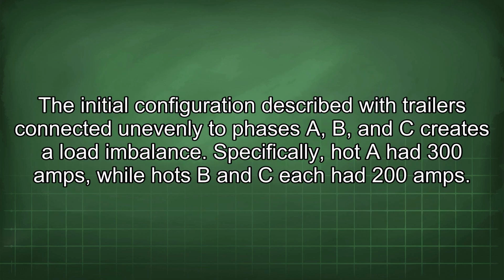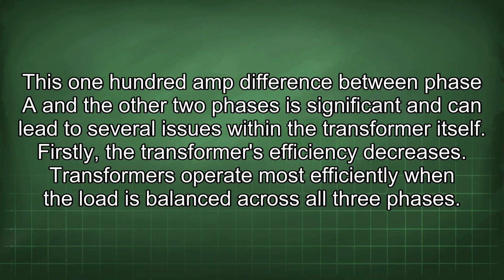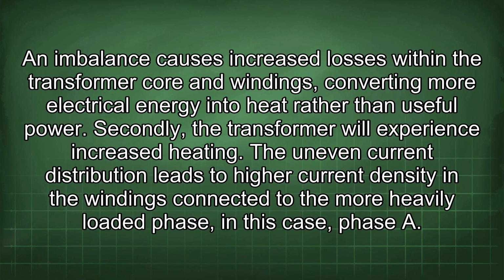The initial configuration described, with trailers connected unevenly to phases A, B, and C, creates a load imbalance. Specifically, hot A had 300 amps, while hots B and C each had 200 amps. This 100 amp difference between phase A and the other 2 phases is significant and can lead to several issues within the transformer itself. Firstly, the transformer's efficiency decreases. Transformers operate most efficiently when the load is balanced across all 3 phases. An imbalance causes increased losses within the transformer core and windings, converting more electrical energy into heat rather than useful power.